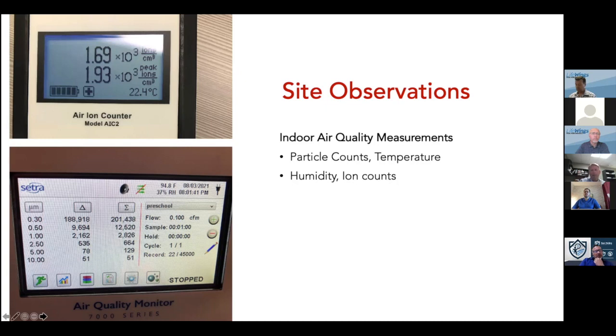In the upper left, the upper photo is actually ion counts. So what we're measuring is the count of ions per centimeter. What we did is measure the peaks. You can see the peak ion count, you multiply it times 10 to the 3, so it's 1900 ions per centimeter cubed. To really get a good ion count, it should be in the 5 to 10,000 range. So it's about half or less of what it really should be. If we have ionization, typically you'd see those numbers in the 5,000 to 10,000 range. So those are some of the things we measure and look at. Humidity and total VOCs are also things that we look at when we're doing the air quality testing. Next slide.